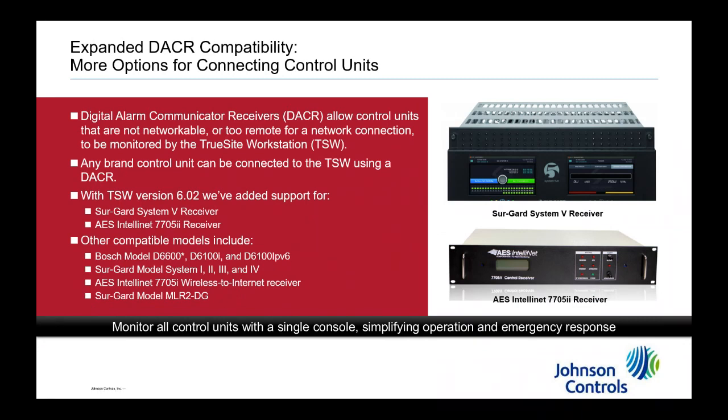Okay. At first blush, this seems like a minor iterative update, right? We've added two new receiver models to our lineup of DACR compatibility. But I'm excited to talk to you about this because I'm excited in general about the DACR. DACR stands for Digital Alarm Communicator Receiver. It's the receiving end of the DACT that goes in the fire panel. And basically, this DACR compatibility allows us to network, for all intents and purposes, with non-Autocall panels.